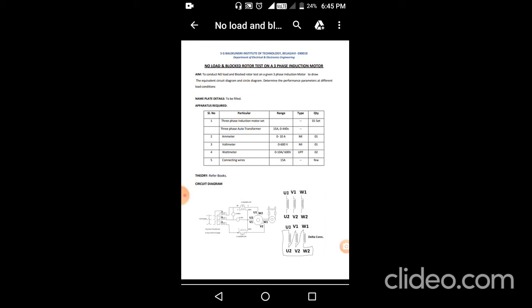With the help of the delta connection diagram we can make the winding connections, because 6 wires are taken out from the actual induction machine, which are given on the 6 terminals on the setup board in the laboratory. These 6 terminals are marked as U1, U2, V1, V2, W1 and W2. So we can connect the induction motor in delta configuration.